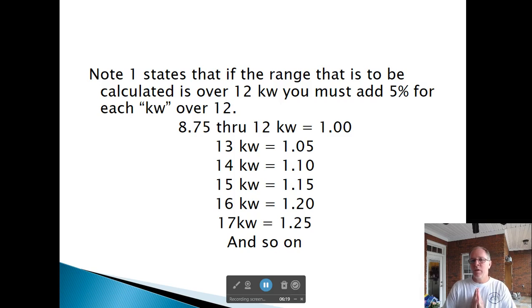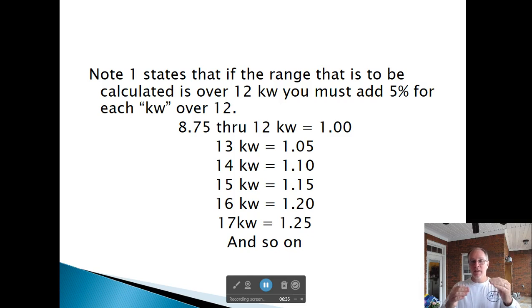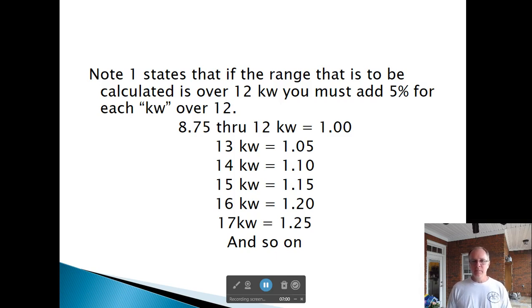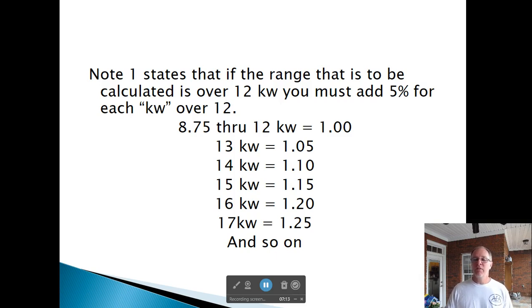What if we've got something bigger than 12 kW? The table is based on 12 kW, so we have to add something. Note 1 below Table 220-55 says: if the range is over 12 kW, you must add 5% for each kW over 12. So a 13 kW range uses 8 kW from Column C times 1.05, and a 14 kW range uses 8 kW times 1.10.